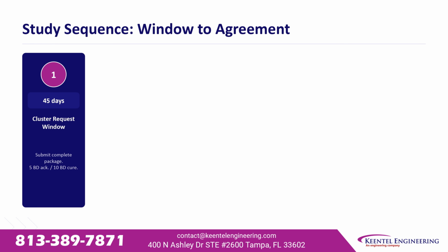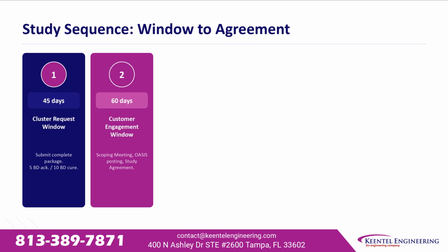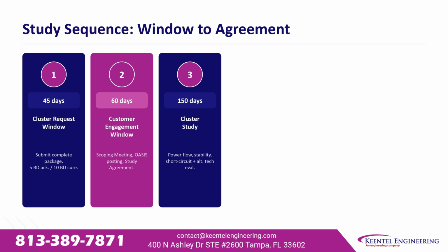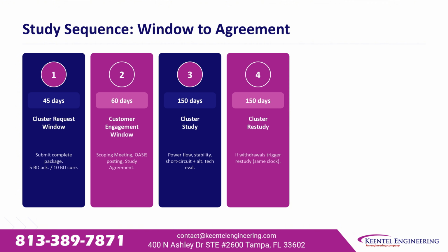The process runs in defined phases. The 45-day cluster request window opens every January 15th. A 60-day customer engagement window follows, including a scoping meeting, OASIS posting of the anonymized cluster list, and execution of the cluster study agreement. Fail to execute and your request is deemed withdrawn. The cluster study then runs 150 days — power flow, stability, short circuit, and alternative technology evaluation across the whole group. Withdrawals can trigger a cluster restudy at another 150 days.